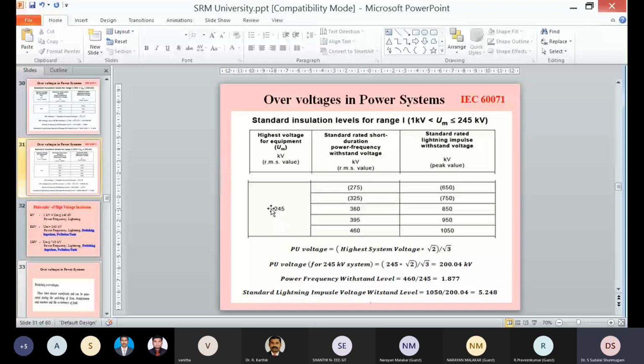I repeat, if I have a 245 kV system, the insulator in that system, I'm just taking insulator as an example, any equipment for that matter, should withstand at least 460 kV of power frequency withstand voltage and 1050 kV of standard lightning impulse withstand voltage.